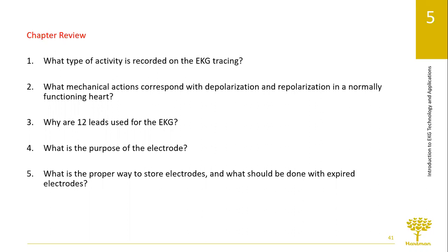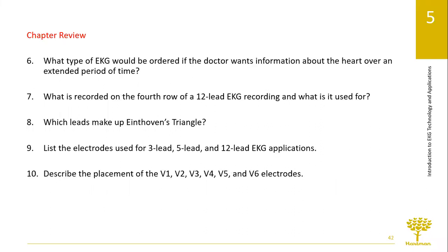And what should be done when they expire is just get rid of them, because when the conductive gel dries out, you don't have good tracing. So it can lead to a wandering baseline. It looks like these undulating waves are going through your strips.